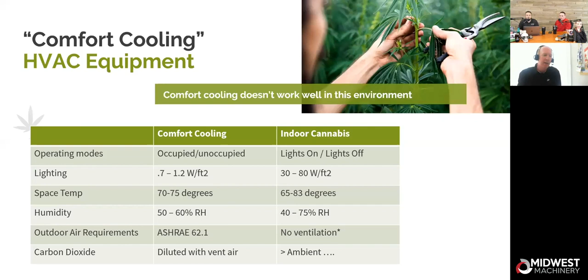When we talk about the inefficient method to do a grow room, it's really the cheap method. It's buying an air conditioner and then buying portables. They are easy to install. They are cheap first cost. You can typically find these off the shelf. That just means you're not doing planning very well if you're just trying to get the first thing available in the market. But the big impact here is you're going to have higher operating costs. Air conditioners are not efficient at moisture removal. They're good at temperature control. That's what they're sized for, but they're not good at moisture removal.